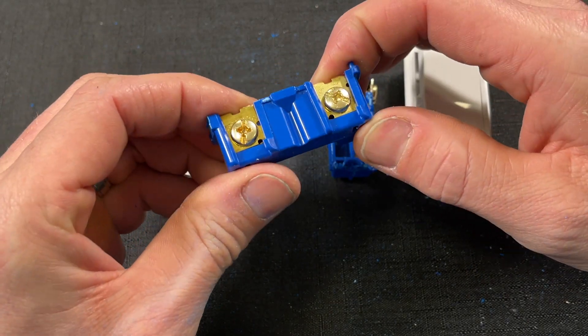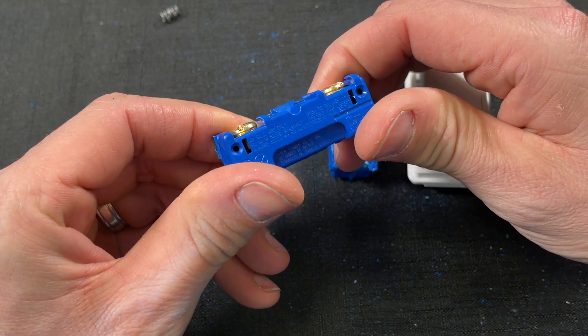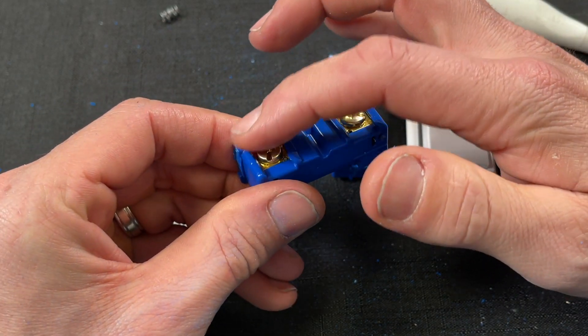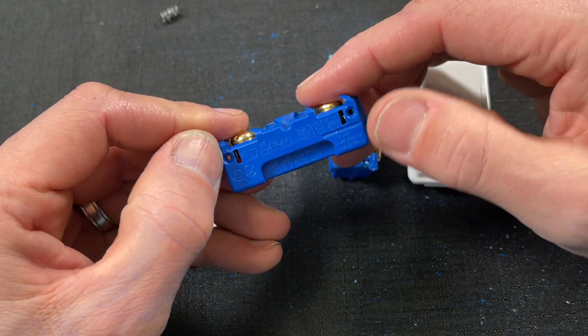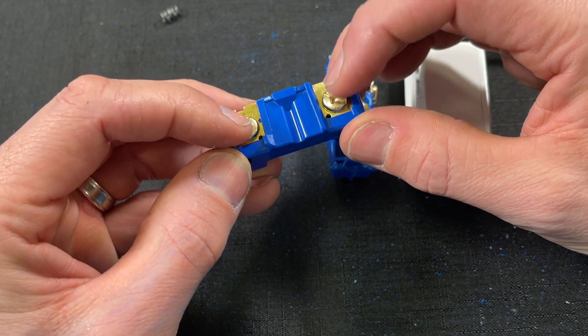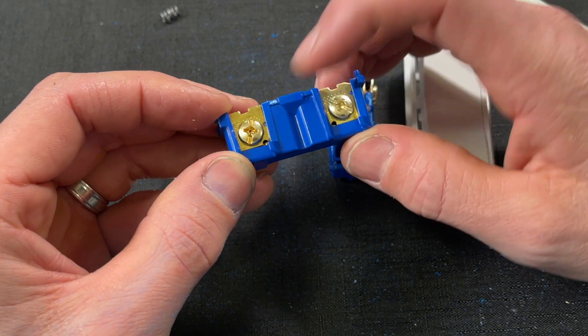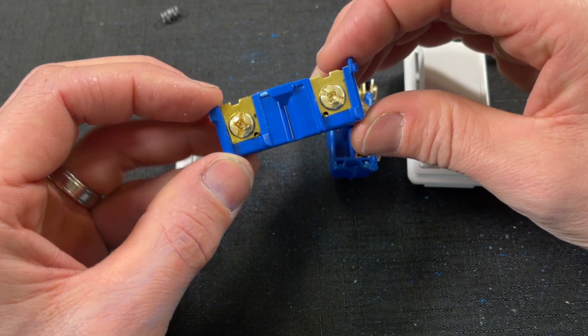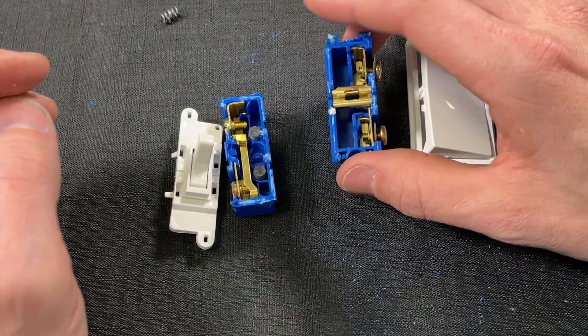Looking at the toggle, you have standard screw terminals that you can wrap in the clockwise direction, or they have push pins — I do not recommend push pins. I would really only use the screw terminals, making a Shepherd's hook or J-hook clockwise around the screws to wire up the switch. I think that process does take a little bit longer.